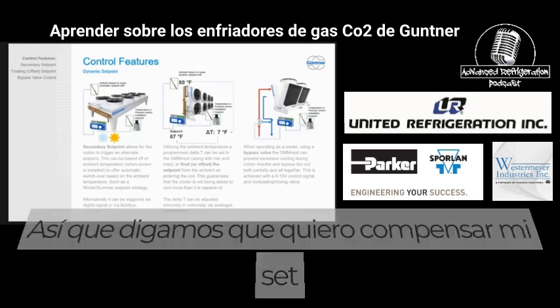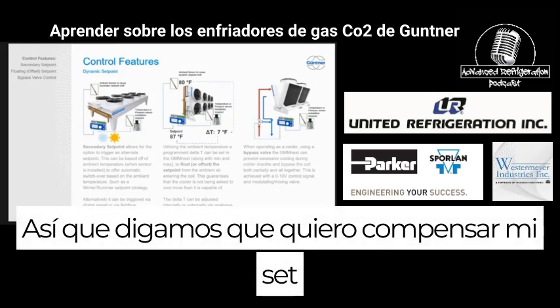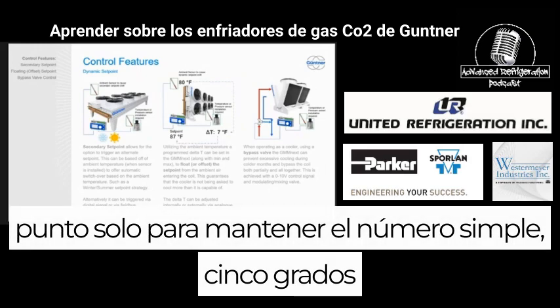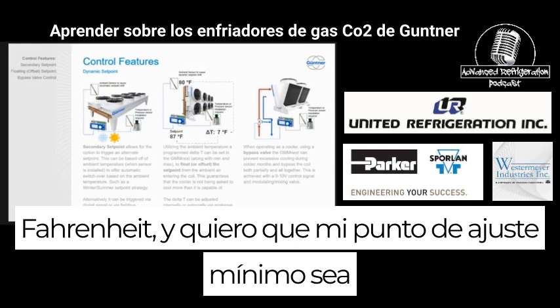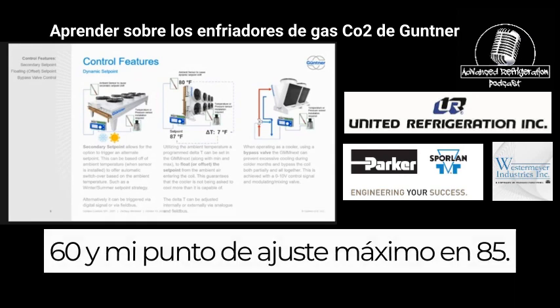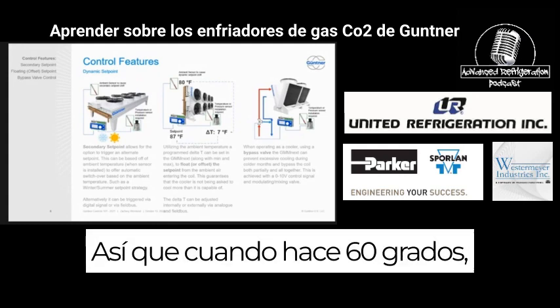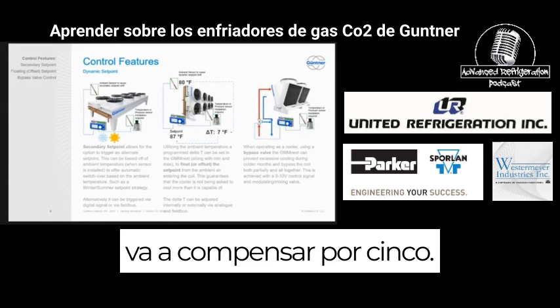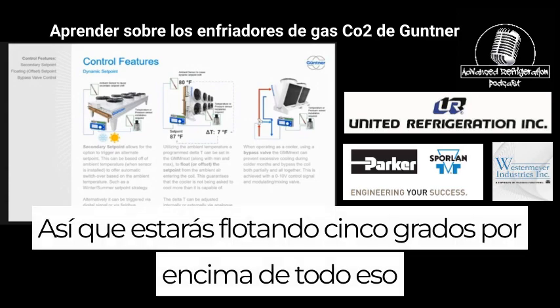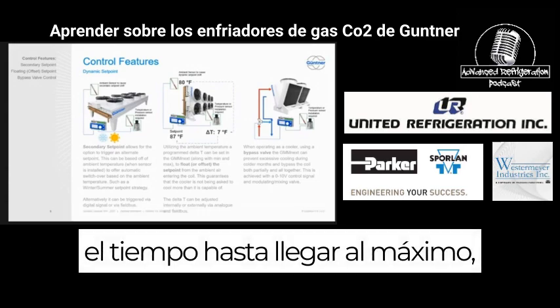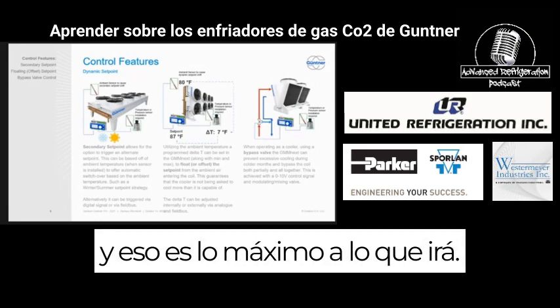So let's just say I want to offset my set point by, just to keep the number simple, 5 degrees Fahrenheit. And I want my minimum set point to be 60 and my maximum set point to be 85. So when it's 60 degrees out, it's going to offset by 5. So you'll be floating 5 degrees above that all the time up until you get to the maximum. And that's the most it'll go to.